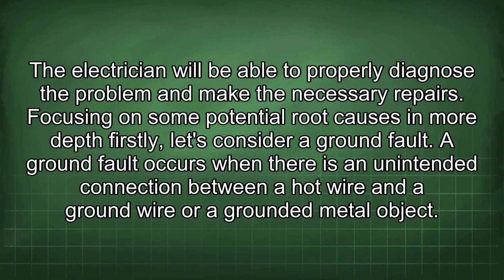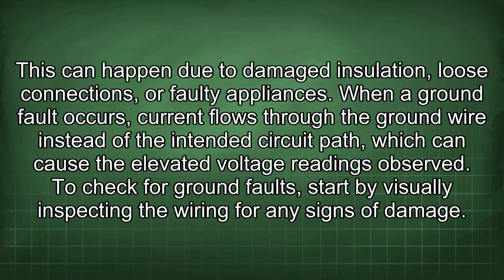Focusing on some potential root causes in more depth, firstly, let's consider a ground fault. A ground fault occurs when there is an unintended connection between a hot wire and a ground wire or a grounded metal object. This can happen due to damaged insulation, loose connections, or faulty appliances. When a ground fault occurs, current flows through the ground wire instead of the intended circuit path, which can cause the elevated voltage readings observed.